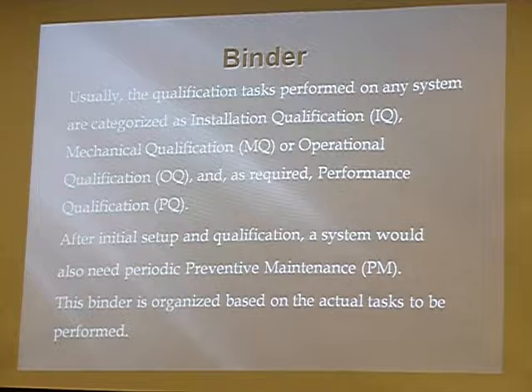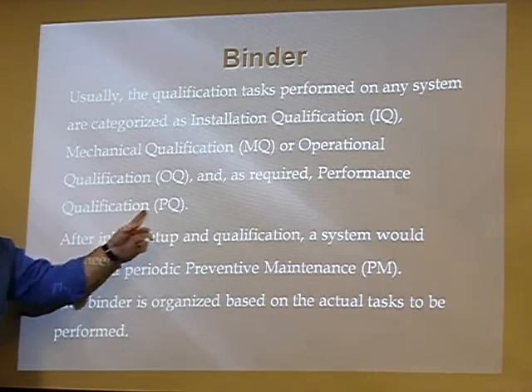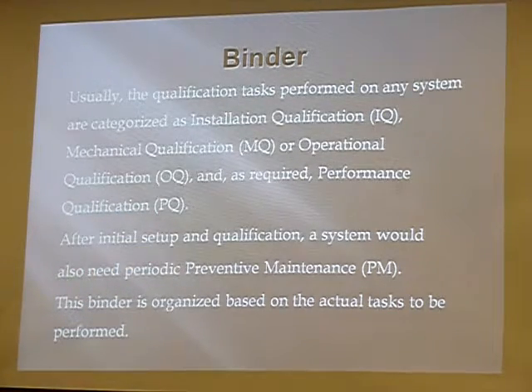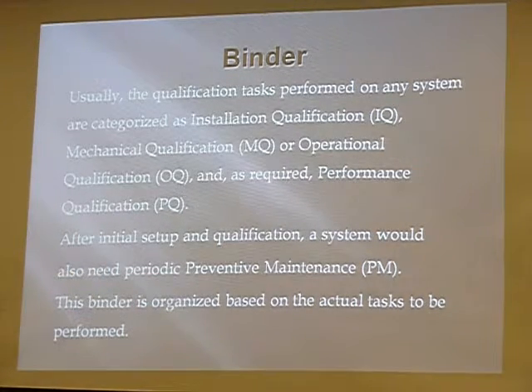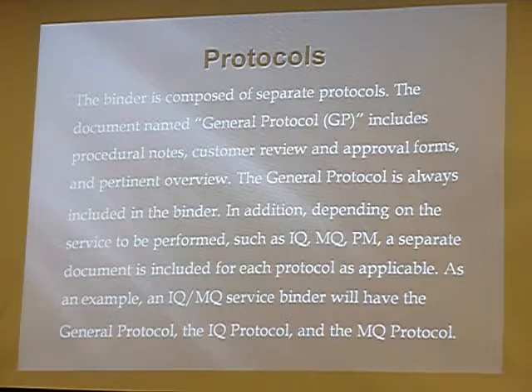The operational qualification is what we're talking about with other equipment, so we don't have to worry about doing mechanical and chemical tests, because we don't do chemical tests on vessel washers and easy fills. So these are the different sections that are in it: IQ, MQ, OQ, and PQ for the PVT, the performance verification test. After initial setup and qualification, the system would also need periodic preventive maintenance, PM. This binder is organized based on the actual tasks that need to be performed. That's how all these binders are put together, in that particular order. And when I say it's put in an order that it needs to be put in, first and foremost, we have general protocol.